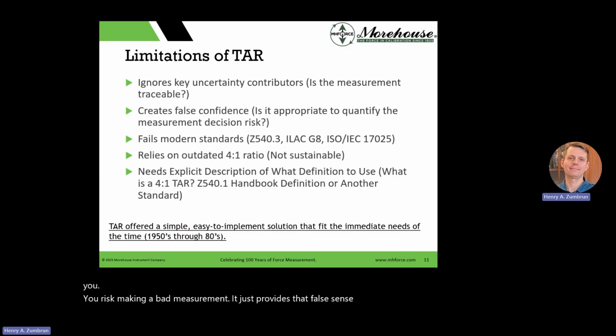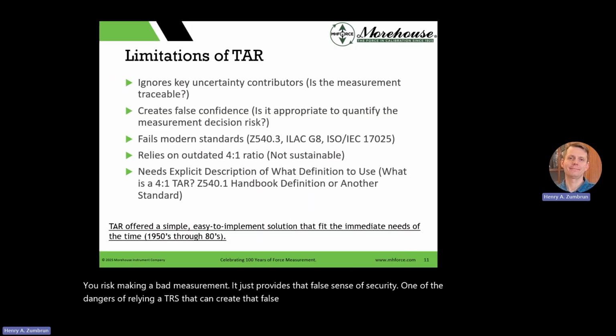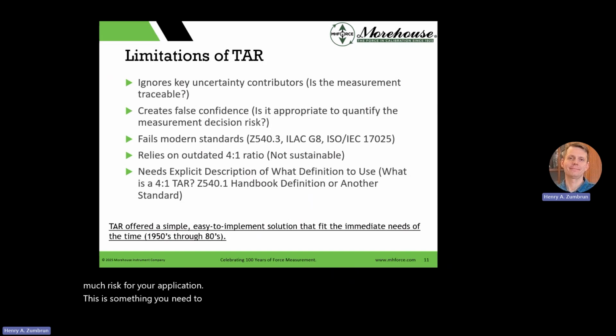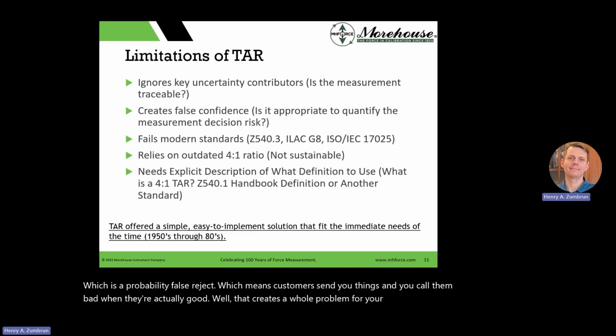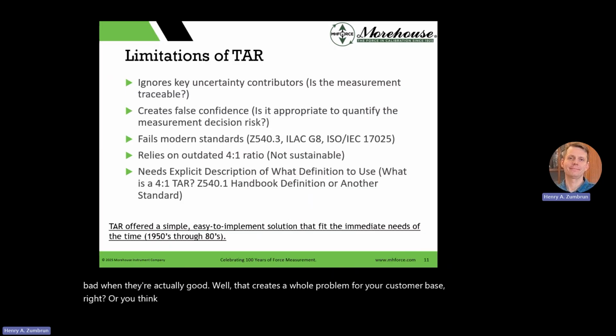One of the dangers of relying on TARs is it can create that false sense of confidence. When I'm at 15:1, I'm really happy, but when I do things correctly, I'm at 1.5:1, which may carry way too much risk for your application. This is something you need to decide because at 15:1, I think the risk is, like I said, super, super low. At 1.5:1, you have a higher PFR, which is a probability of false reject, which means customers send you things and you call them bad when they're actually good. Well, that creates a whole problem for your customer base, right? Or you think you have a super huge acceptance limit when you really don't, because an acceptance limit at something that's 15:1 is microscopic. If you're at 1.5:1, it's quite large.